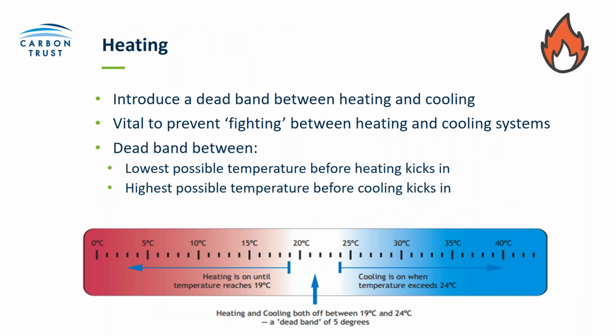Another thing to really make sure you have in place is this dead band. So as you can see from the thermometer scale at the bottom, you want to have a period in the middle where heating and cooling neither of them are on. This is to stop the fighting between the different systems. So you have a dead band where you wait for the temperature to hit the lowest possible temperature before you start heating, and you wait until you reach the highest possible temperature before you start cooling.